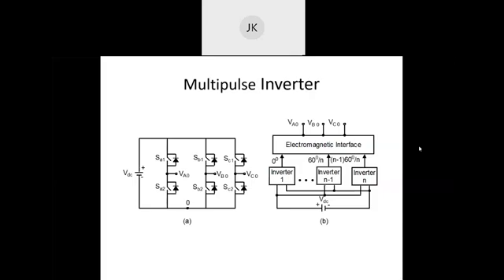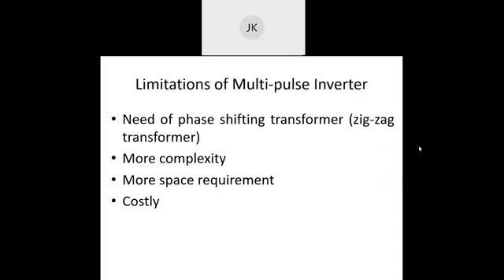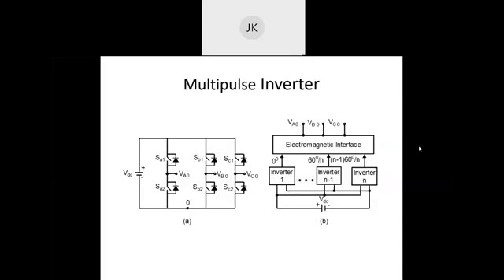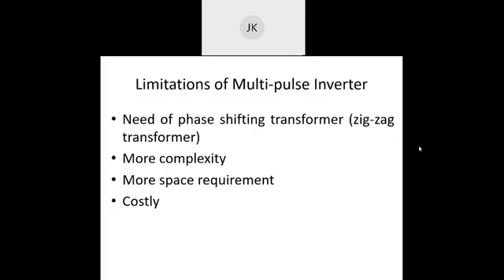In initial research work, STATCOM - a reactive power compensating device - was developed based on multipulse inverters. But the problem with this type of inverter is the need for a phase shifting transformer, because we have to integrate all these units using the zigzag transformer. This requires more space, more complexity, and the cost also goes up.